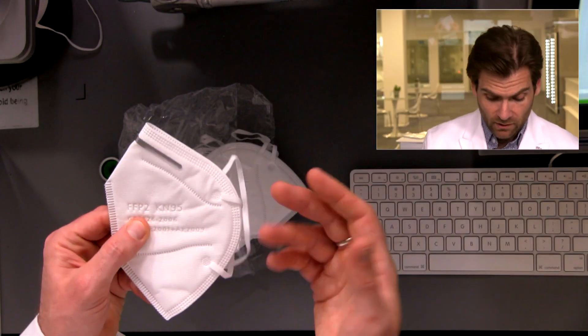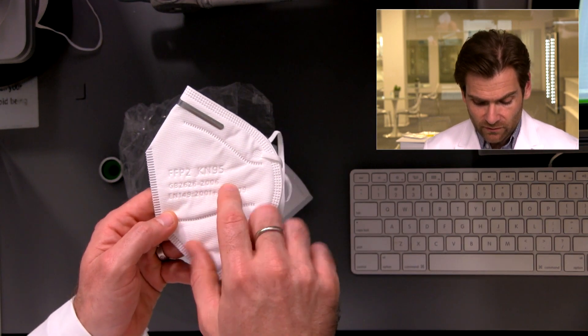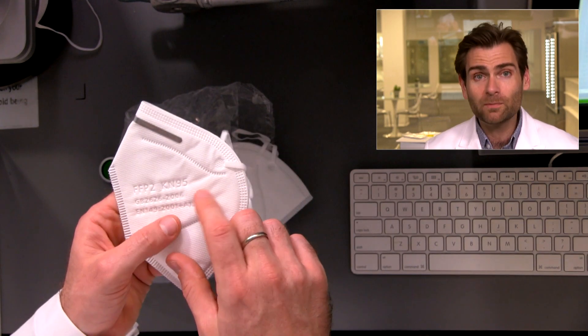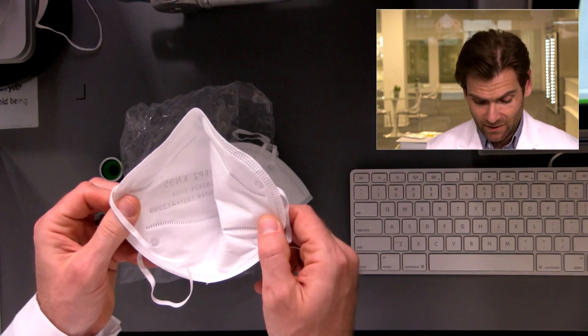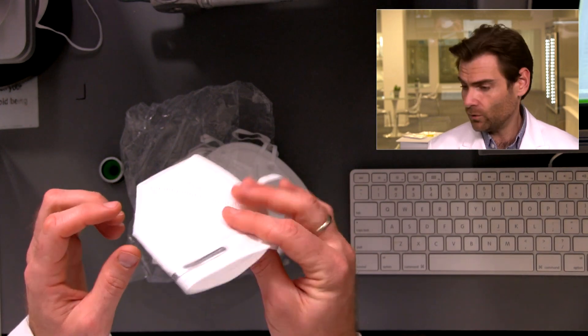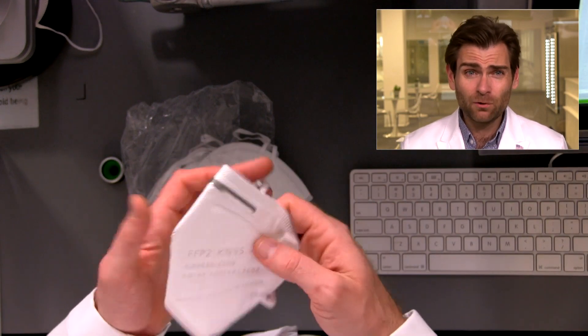This is claiming to be a KN95 and an FFP2, which is a European standard for this type of respirator. You can see right here: GB2626-2006. It's almost meeting the standard — the thing it's missing is the manufacturer name or brand name, which has to be on there. That's not on here, so for some reason they're not fully meeting the standard.